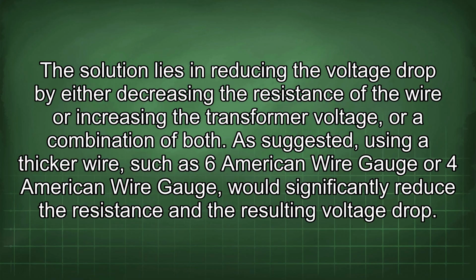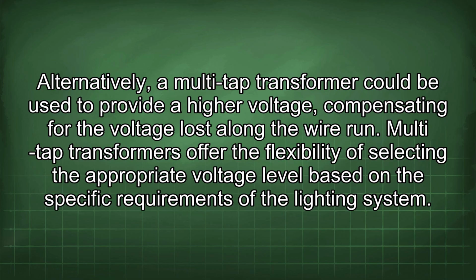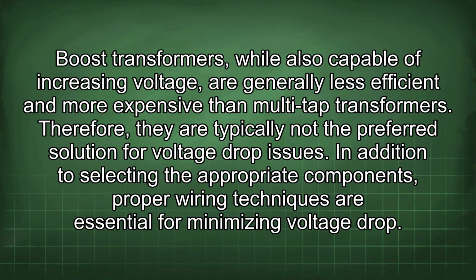As suggested, using a thicker wire, such as 6 American wire gauge or 4 American wire gauge, would significantly reduce the resistance and the resulting voltage drop. Alternatively, a multi-tap transformer could be used to provide a higher voltage, compensating for the voltage lost along the wire run. Multi-tap transformers offer the flexibility of selecting the appropriate voltage level based on the specific requirements of the lighting system. Boost transformers, while also capable of increasing voltage, are generally less efficient and more expensive than multi-tap transformers. Therefore, they are typically not the preferred solution for voltage drop issues.